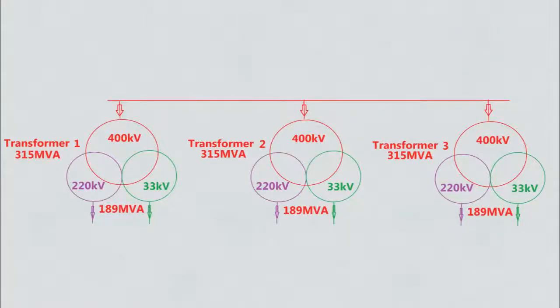Now, with an example let's see how parallel operation of transformers is done. As shown in the diagram, let's consider a substation with 3 transformers each rated 315 MVA and 400/220/33 kV — that is Transformer 1, Transformer 2, and Transformer 3 — all with the same impedance. The 400 kV side is the incoming side and 220 kV and 33 kV are the load sides. Assume all transformers are in service and around 60% loaded, meaning each transformer has 189 MVA load, totalling 567 MVA across all 3 transformers.